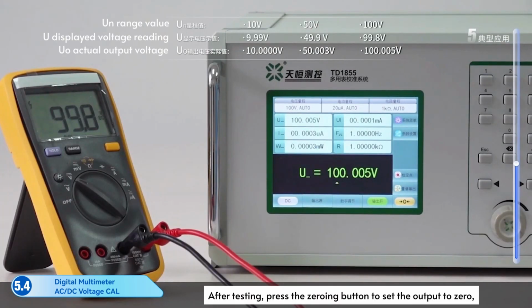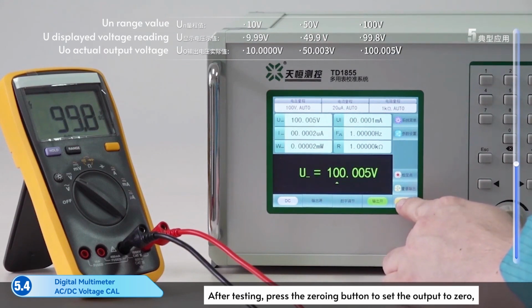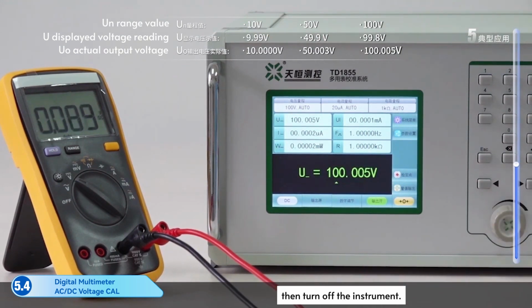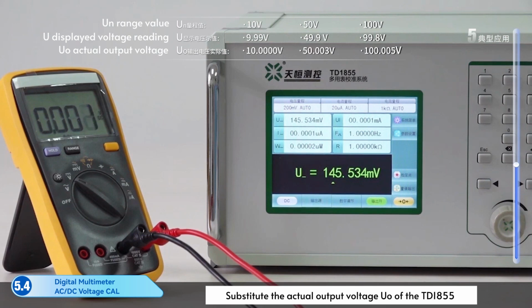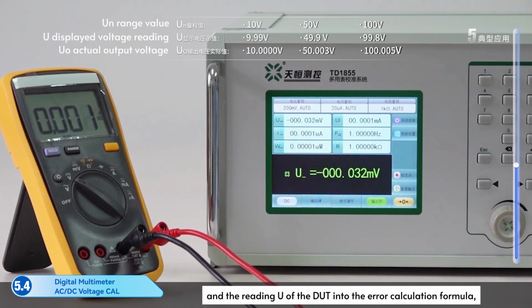After testing, press the zeroing button to set the output to 0, then turn it off. Substitute the actual output voltage and the reading of the DUT into the error calculation formula. Calculate the errors for each calibration point and record them in the report.